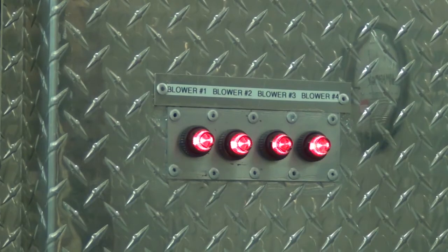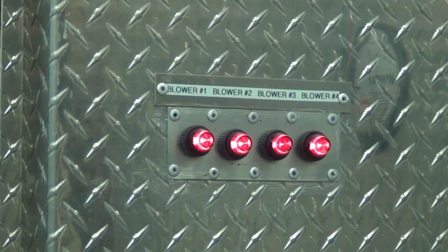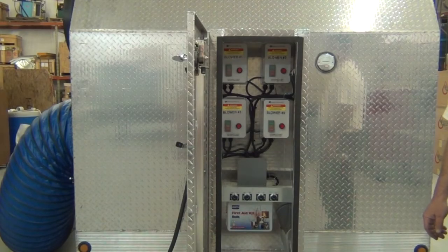Now we have all 4 blowers running. Everything's been stabilized. We're actually moving about 30,000 CFM of air because the ductwork is not hooked up and the blowers are certainly running at their maximum effort. This will actually provide more of a pressure drop across the filters than normally designed. We'd expect about 1¼ inches at full 18,000 CFM or so flow. With the blower now up to speed, we're actually circulating air through the HEPA filter section.